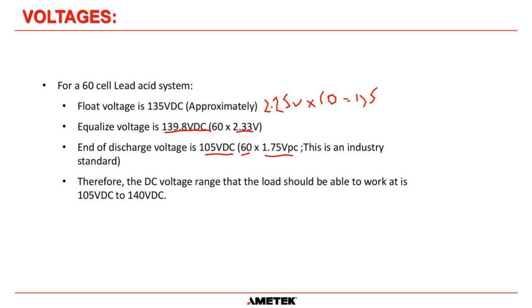In the industrial world, that's usually taken as 1.75 volts per cell. So if you multiply your 60 cell system times 1.75, you get 105 volts DC. These calculations tell us the DC voltage range that the loads on this battery should be able to work at is anywhere between 105 to 140 volts DC.